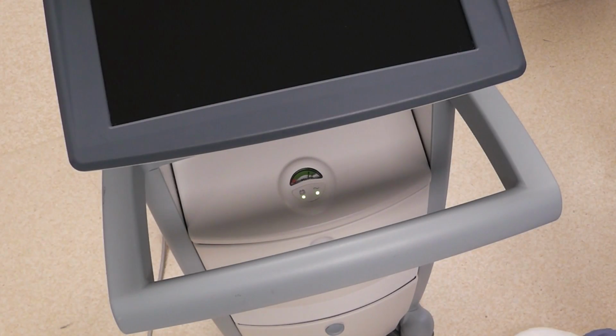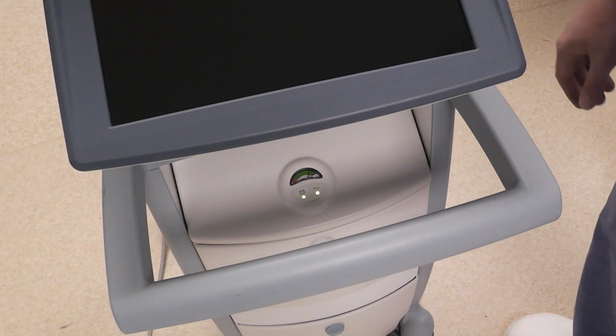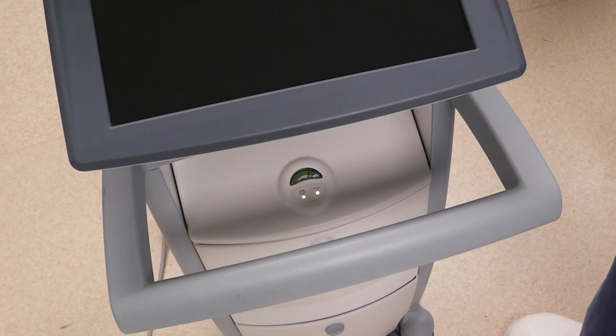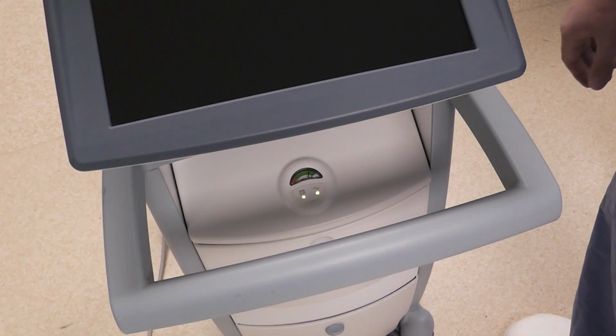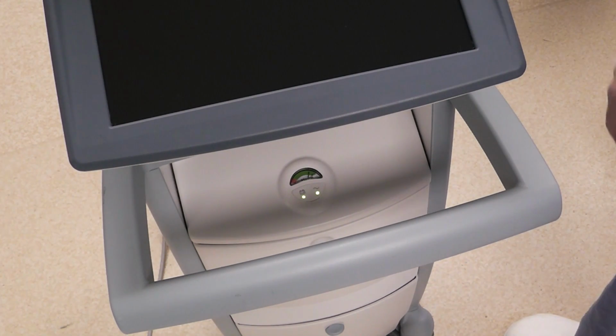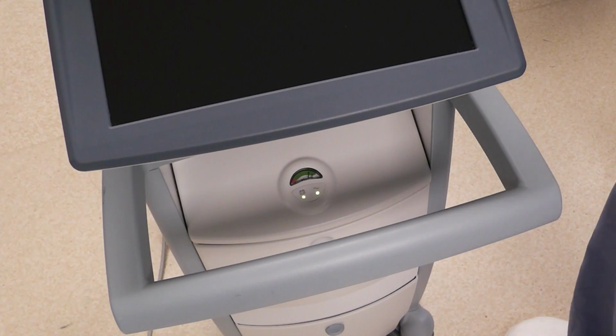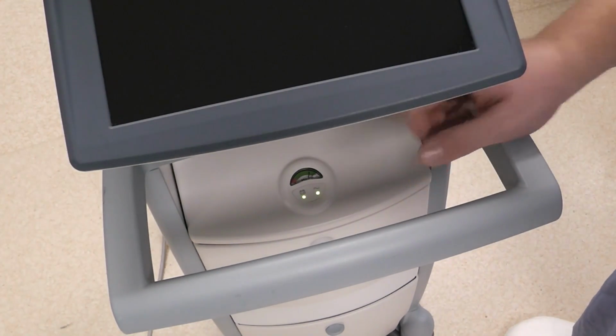Before we even bother turning the machine on, we need to check the helium gas levels. Helium is the gas that these balloon pumps use to shuttle back and forth to the balloon. The way we check the helium is by checking the pressure gauge. On this particular unit, the gauge is on the front. You can see it's right below the screen and above this handle.